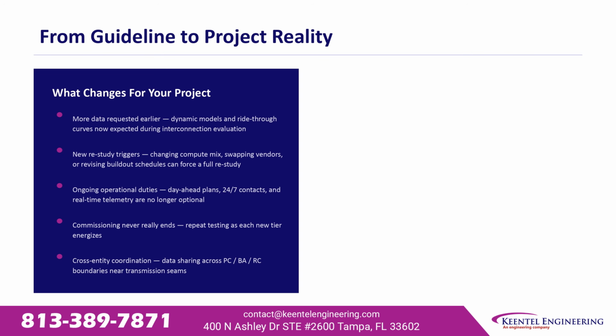So what actually changes for your project? More data gets requested earlier. Dynamic models and ride-through curves are now expected during interconnection evaluation. New restudy triggers mean a changed compute mix or a revised build-out schedule can force a full restudy. Operational duties don't end at energization, and commissioning repeats as each new tier comes online.